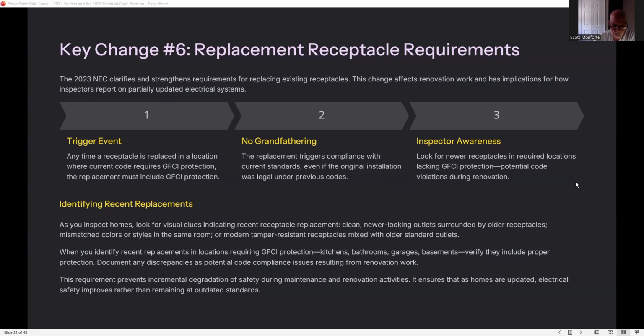Identifying recent replacements. As you inspect homes, look for visual clues indicating recent receptacle replacement: clean, newer looking outlets surrounded by older receptacles, mismatched colors or styles in the same room, or modern tamper resistant receptacles mixed with older standard outlets. When you identify recent receptacles in locations requiring GFCI protection, such as kitchens, bathrooms, garages, and basements, verify they include proper protection. Document any discrepancies as potential code compliance issues resulting from renovation work.